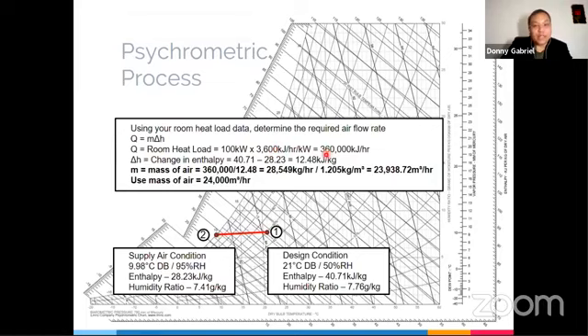So we will convert it to 360,000 kilojoule per hour. So by using this 360,000 kilojoule per hour and this change in enthalpy, we will get the amount of air needed in kilogram. So using our formula, Q is equal to M delta H, M is the mass of air. We will get about 28,000 kilograms of air per hour. Using our air density, we will get 23,900 cubic meter per hour. So let's round it off. Let's say 24,000. So to cool down the room from 9.8 to 21, you would need 24,000 cubic meter of air per hour.